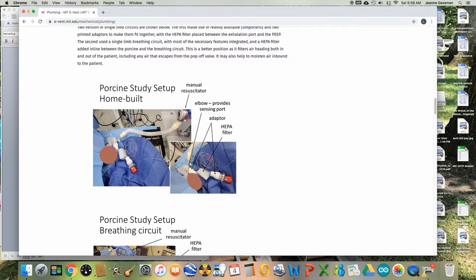However, all designs have the same problem of dead space. The tube connecting the ventilator to the patient is four to six feet long, and the volume of air in it is called dead space. When a patient exhales, the space is filled with carbon dioxide which the patient may then rebreathe on the next breath. MIT's solution was to move a set of valves close to the patient's mouth or endotracheal tube, which allows inspired gas to be pushed into the patient but expired gas to be quickly vented by a second tube away from the ventilator.